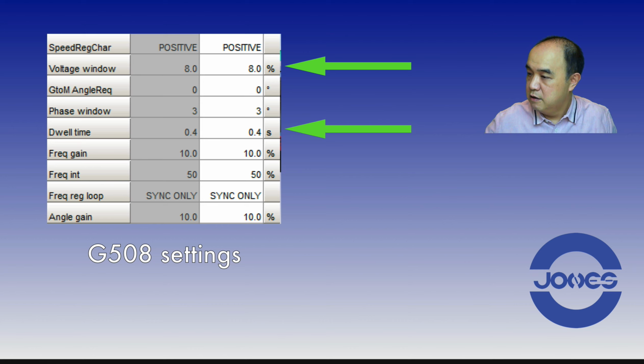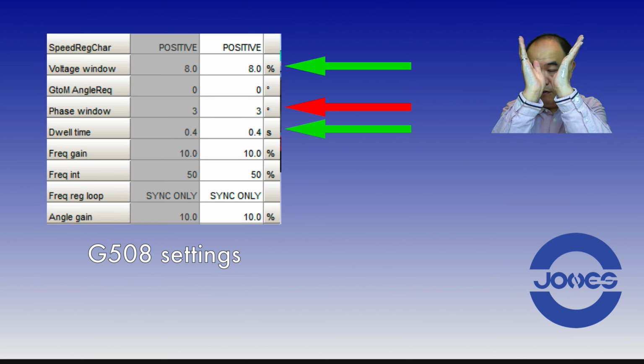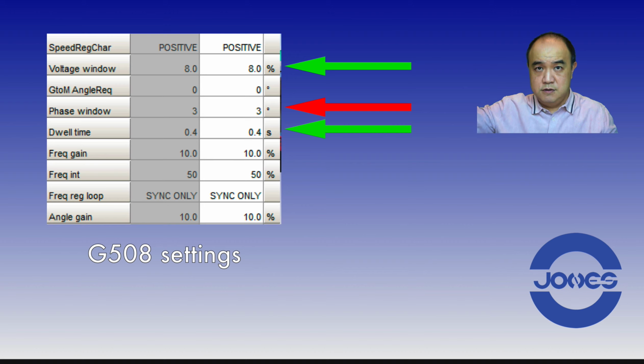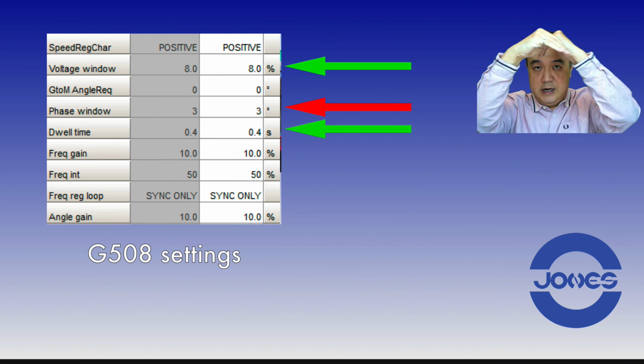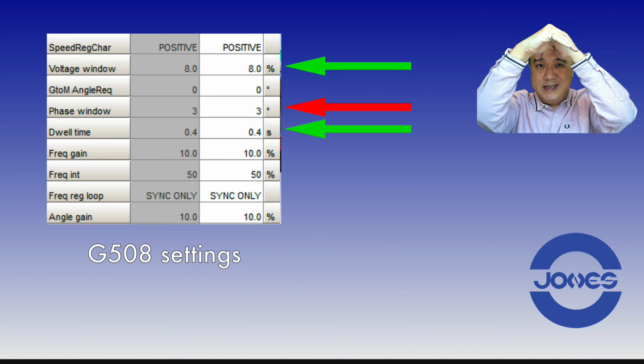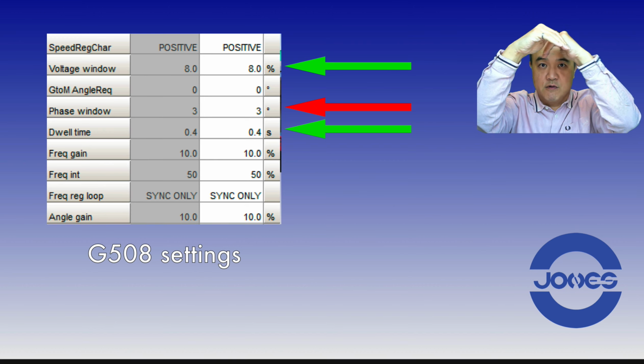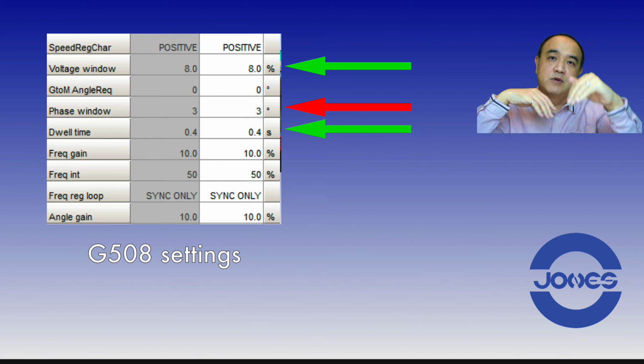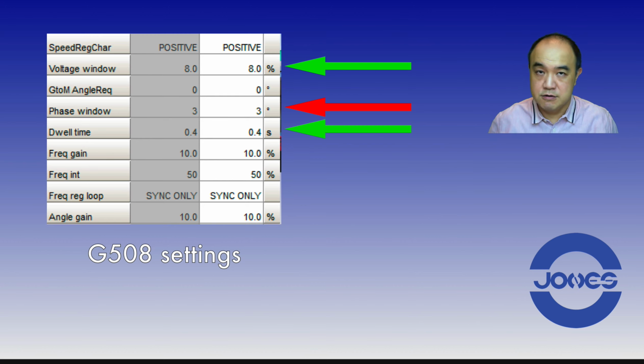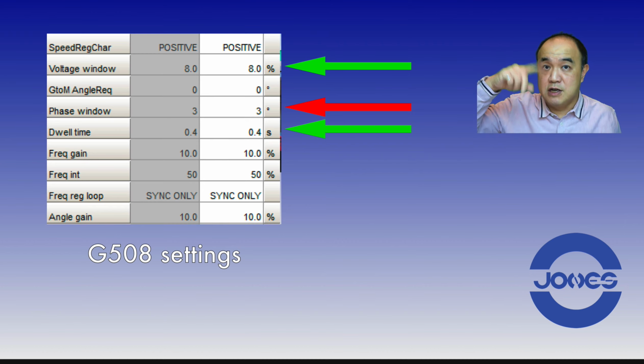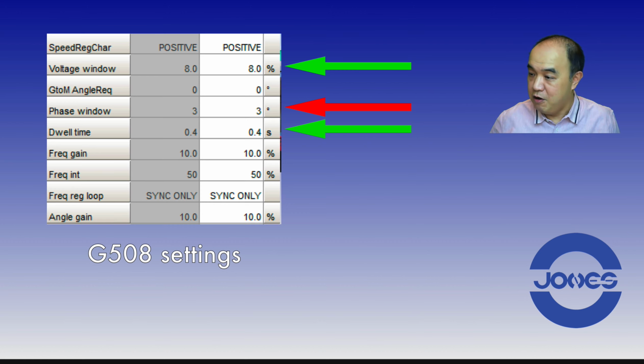That's okay. What I didn't like to see is the phase window of 3 degrees. What this means is the two sine waves of the two gensets have to overlap within 3 degrees for 0.4 seconds before we will send a synchronous signal, so thereby we will ask the breakers to close. Of course, 3 degrees when the engine speed is going up and down like that, that is not going to happen very often, that we can hold 3 degrees at 0.4 seconds.